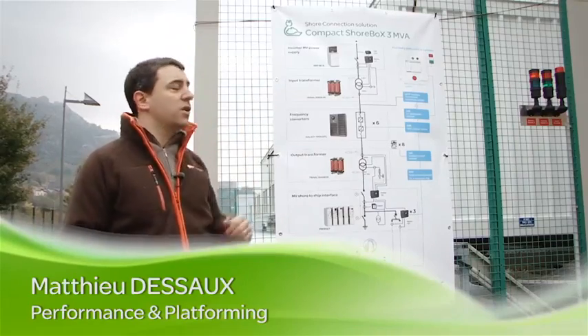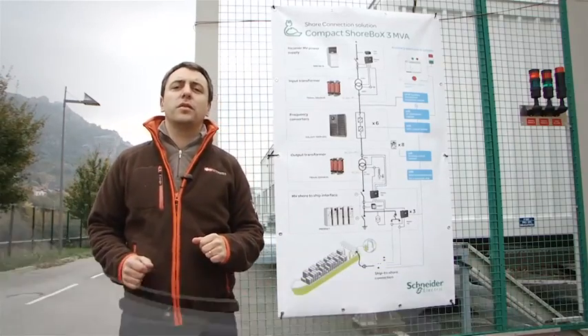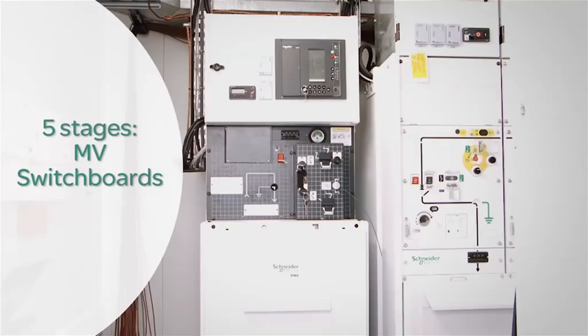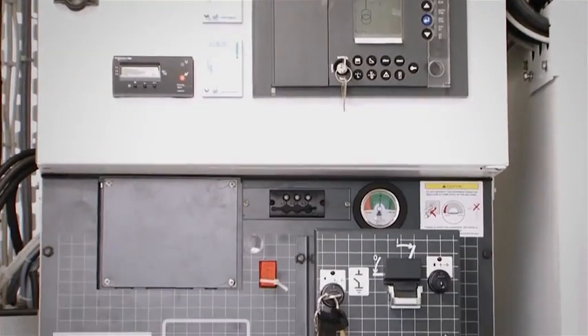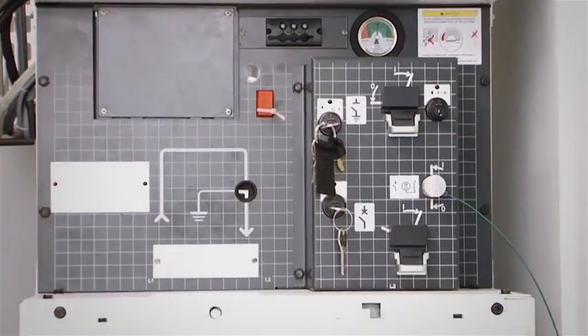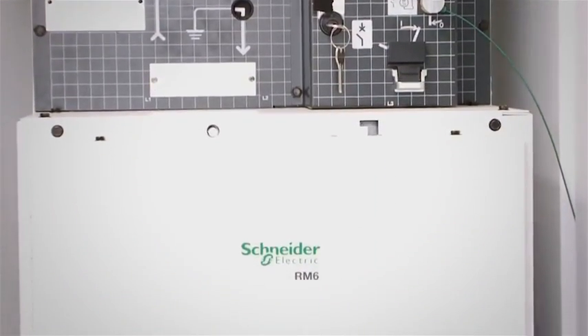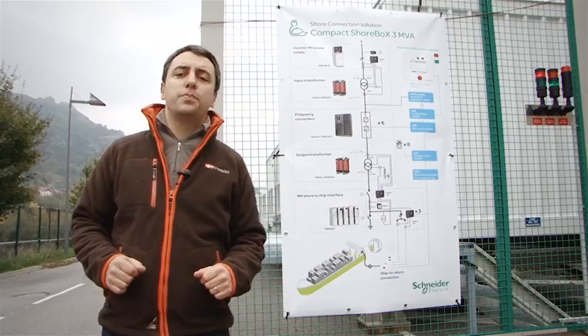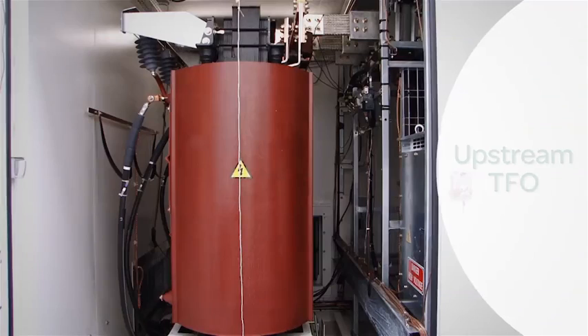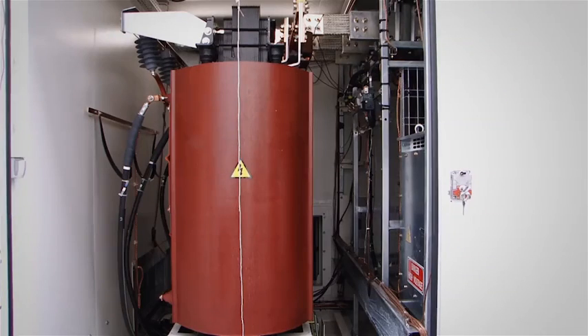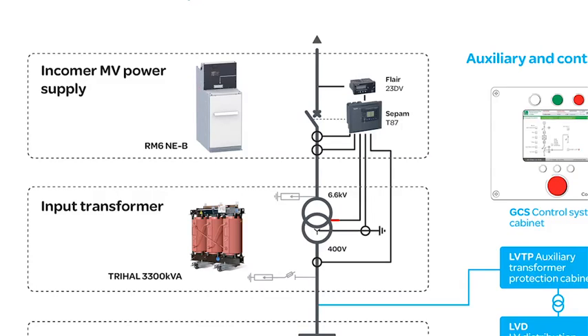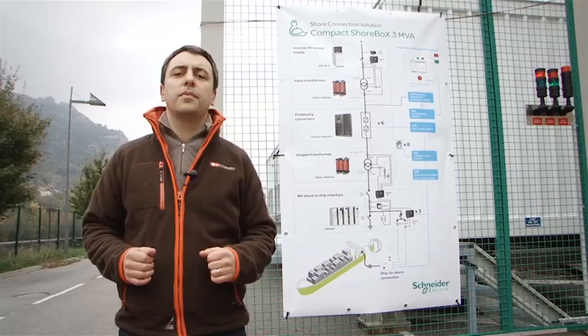The first stage consists in connecting the ShoreBoX to the grid. It is made through a medium voltage circuit breaker type RM6 with a rated voltage from 5.5 kV up to 24 kV. Downstream we will find the first medium voltage dry type power transformer with rated power of 2200 kVA or 3300 kVA. Its role is to lower the voltage to 400 volts.